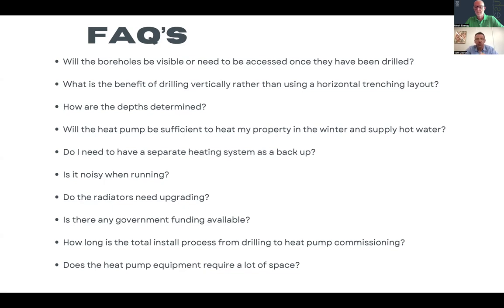And if you install a 20 kilowatt system now and do the cavity wall insulation later, of course your efficiency will improve and running costs will drop, but you initially spend for 4 boreholes and a slightly bigger heat pump, where you could install, let's say, a smaller heat pump with 3 boreholes.